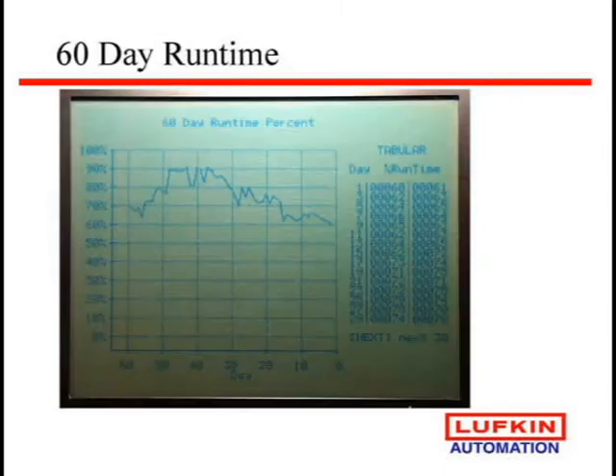Most all of these have a lot of data stored in the controllers, but most controllers, to save money, only keep about 60 days of data, and then they ask for the rest of the data to be stored up in a host system or a SCADA system that we bring the data in through a communication device.